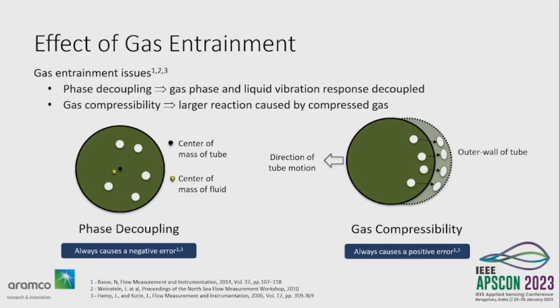Basically this acts like a dampener, like the suspension in your car. It absorbs the vibration imposed on the tubes, and this always ends up causing a positive error, because the compressed gas exerts a larger force on the tube.